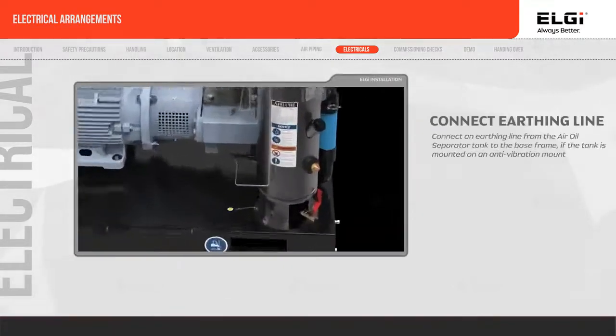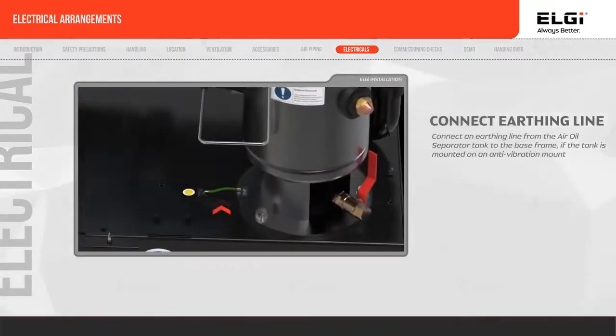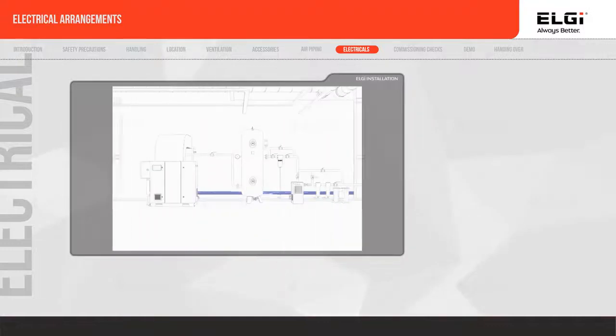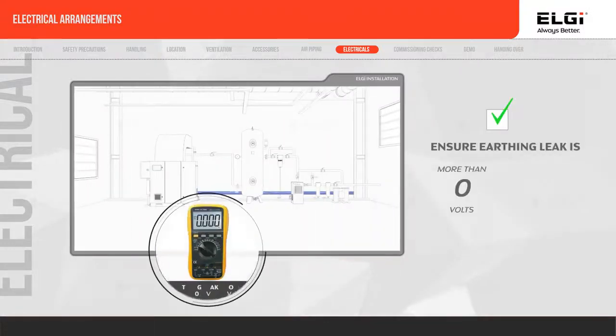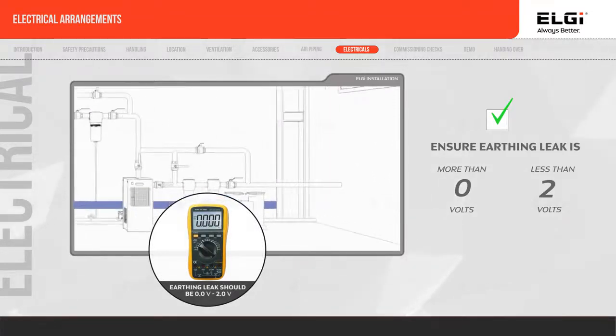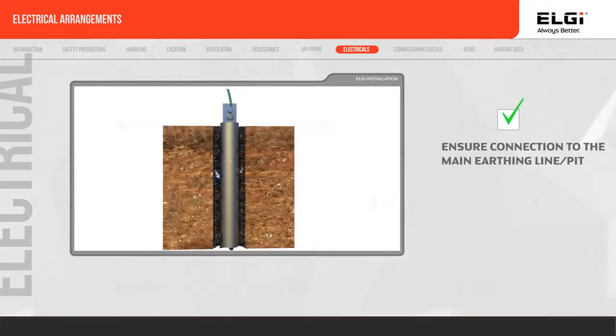Connect an earthing line from the air oil separator tank to the base frame, if the tank is mounted on an anti-vibration mount. Ensure that the earthing leak is greater than 0 volts and less than 2 volts. Ensure the compressor earthing line is connected to the main earthing line, which is connected to the earthing pit.